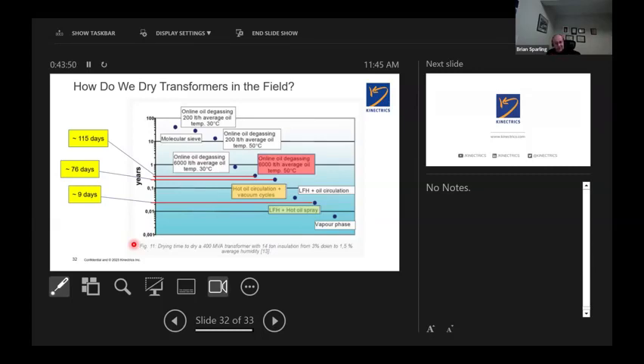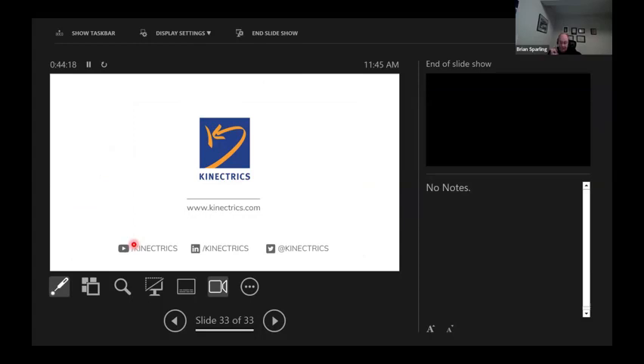Vapor phase, you see on the far right-hand side, far less. That's the process that's used in a transformer factory. Vapor phase drying of the core and coil assembly in the factory. But heaven forbid, you're not going to send this back to the factory to be dried. So low frequency heating does 2 things. It dries out more efficiently, to a better result, in a much shorter period of time. And time is money to a utility and the operation of a transformer. So that's where we are, Randy, with moisture and low frequency heating of drying a transformer.